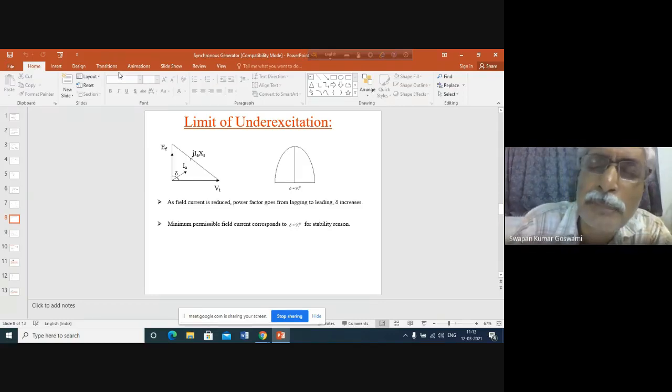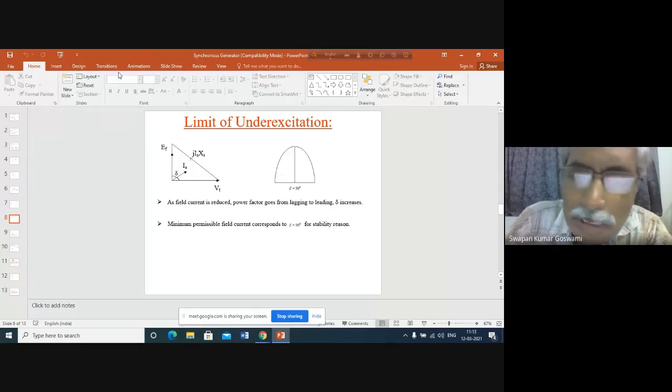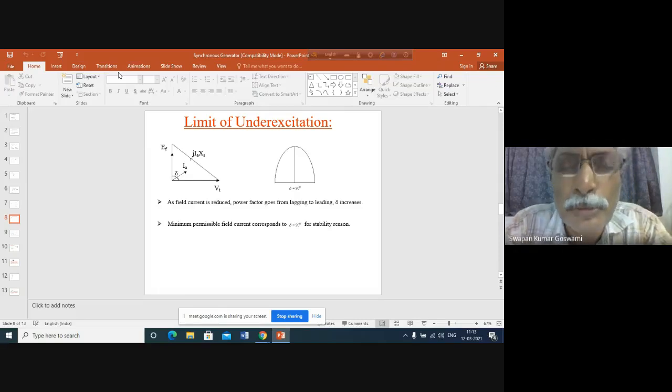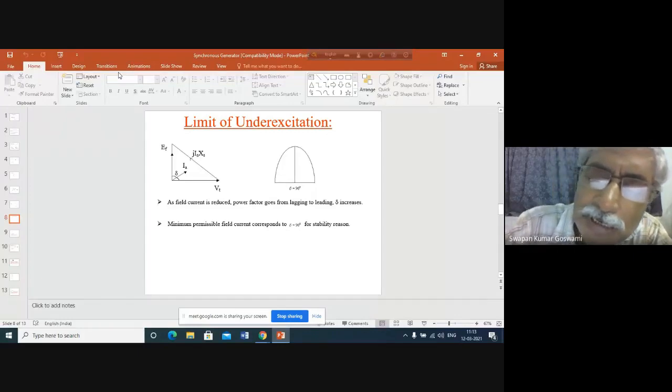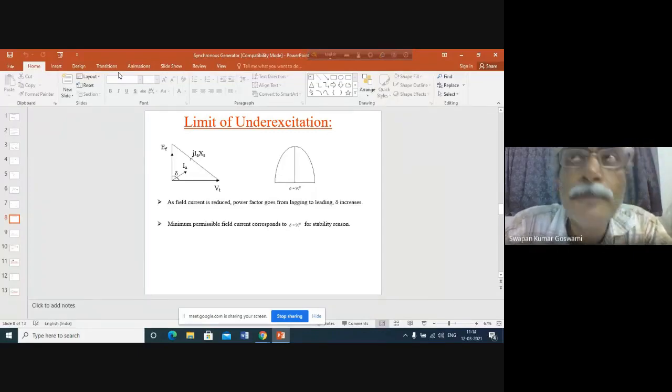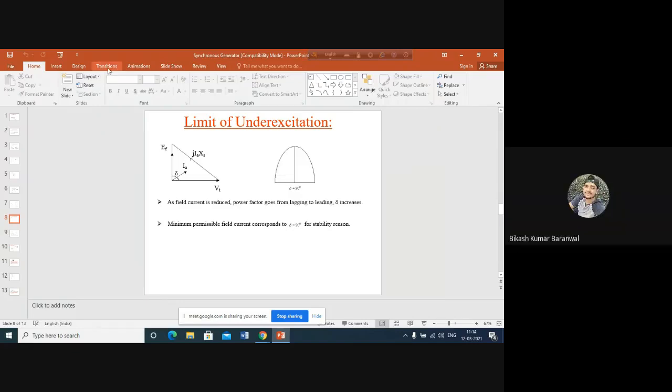In respect of active power, it will be a generator obviously, but in respect of reactive power, generator will be now consuming reactive power. How? The excitation of the generator will be reduced. So if the excitation is reduced, then generated voltage will be reduced. If the generator voltage is reduced, then obviously system has a tendency to increase its voltage, so generator will be able to maintain constant voltage if it consumes reactive power from the system. Am I clear? বুঝতে পেরেছো? Is it clear? Yes, sir.